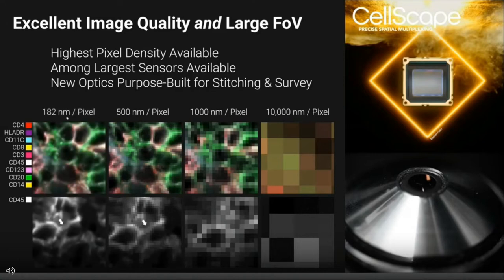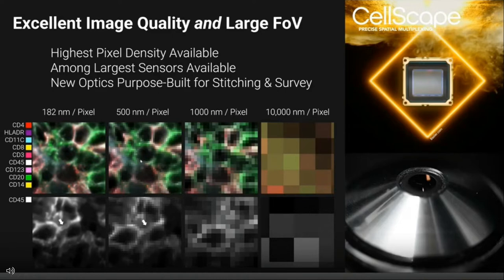The Cellscape can actually collect images at 182 nanometers per pixel, so the image is absolutely crisp. At 500 nanometers per pixel you can certainly do cytometry — separate individual cells and assign signal accordingly. But 182 nanometers per pixel allows us to truly say that we have subcellular resolution. The ability to see these smaller subcellular features is what's going to power the next step of chip cytometry and cytometry in general: not just locating where a signal is on a cell, but locating where a signal is in a cell.